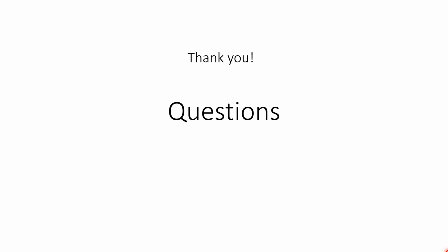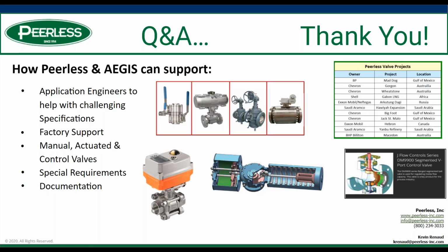As you increase in pressure for our control valve applications, it depends on the type of turn down that is required, the CVs that are required, and the flow conditions. So to answer that, it's very simple for us. If it's 100 pounds or less and something that we can control fairly easily, we will use a V-ball. If it's something that is above 100 pounds and we have temperatures involved, flow conditions, we can use our segmented valve.